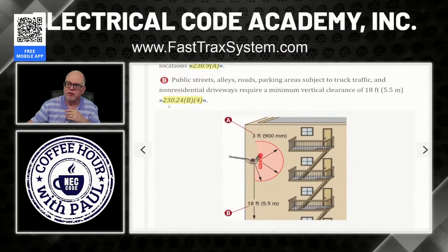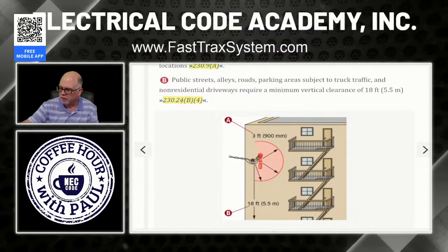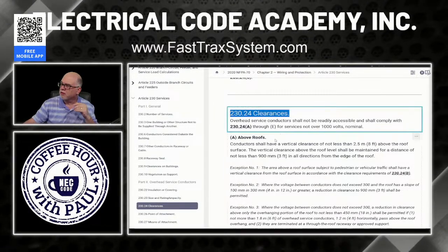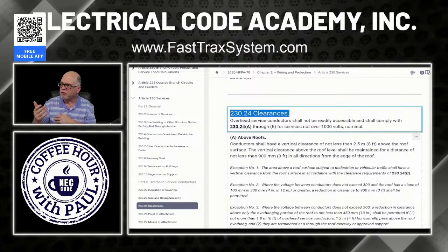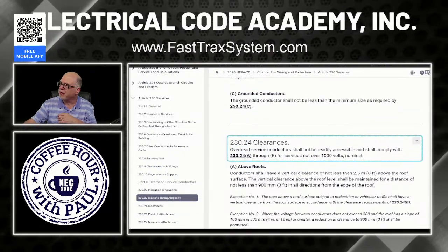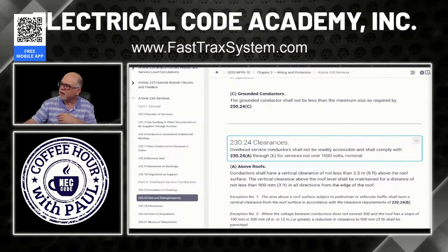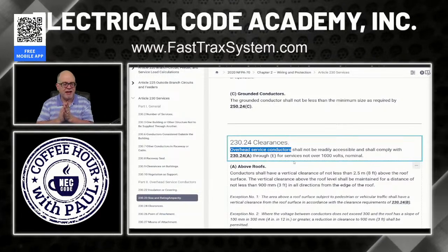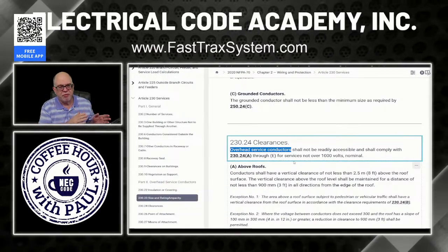So take your code books. Let's go to 230.24(B)(4). I'm going to go there. And we're already here, obviously, because we were on clearances. So remember, .24 seems to be clearances, right? But you'll notice that when it talks about clearances here, notice what it says. It says overhead service conductors. It does not say service drops.